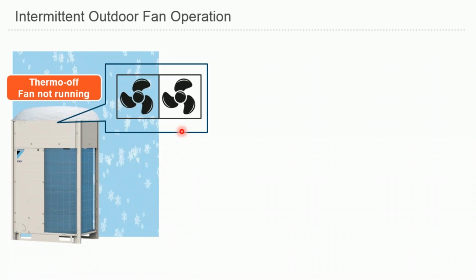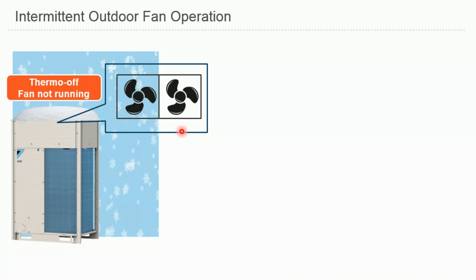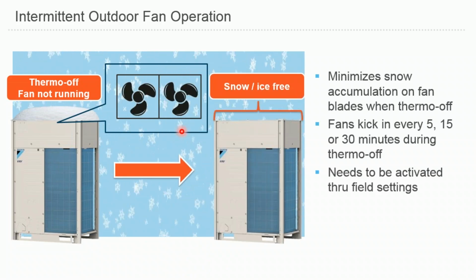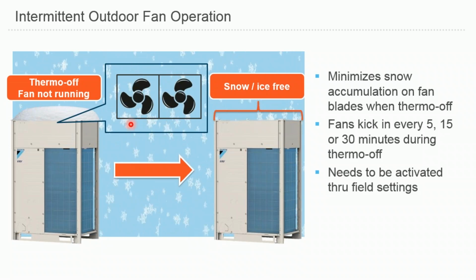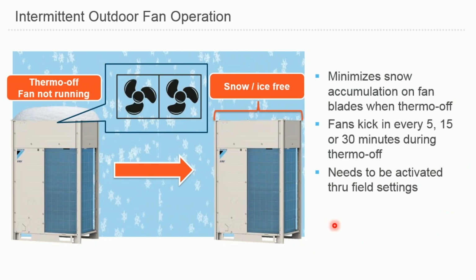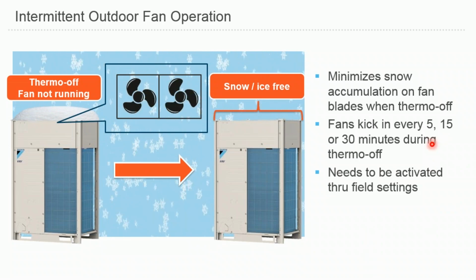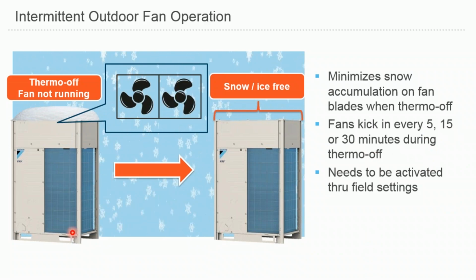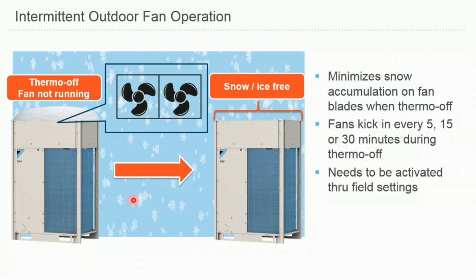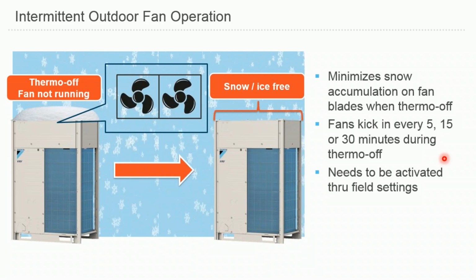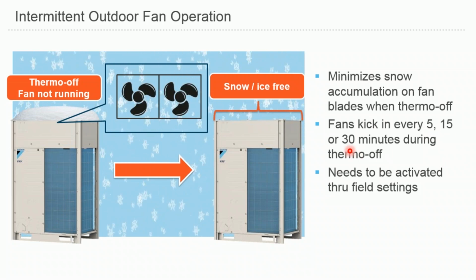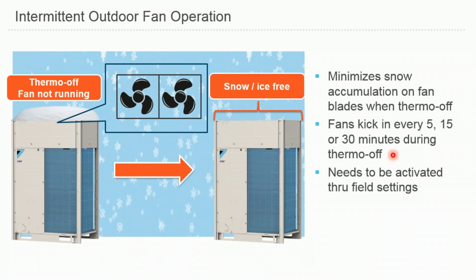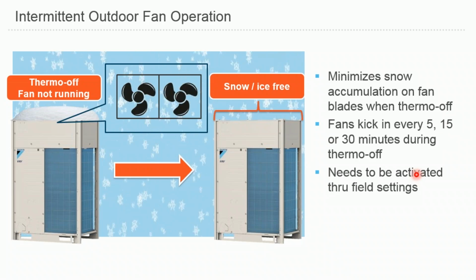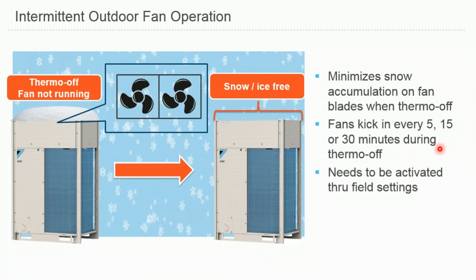So to avoid that problem, we're adding some additional field settings for this intermittent outdoor fan operation. Basically, to avoid this ice accumulation at the top, if you activate this field setting, your outdoor unit fan will kick in every 5, 15, or 30 minutes even when your compressor is not running during thermo-off mode. And this 5, 15, or 30 minutes will be totally up to you. Whatever setting you want to use, the field setting will be different, and you will go from there.